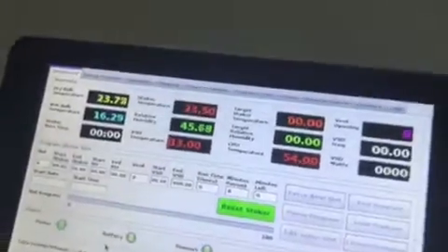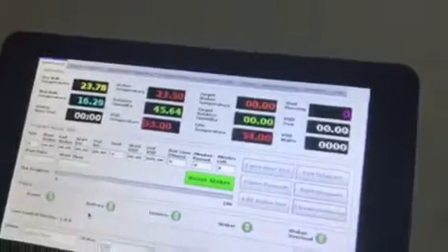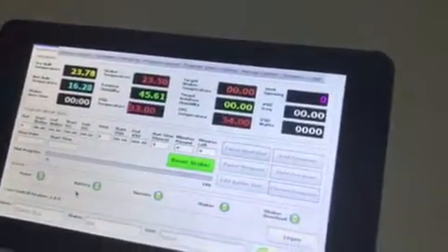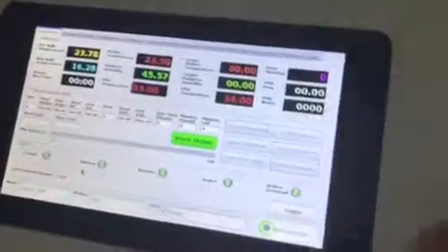So there we can see wet bulb, dry bulb, the stoker temperatures, how big the vent opening is, and there's a whole control cycle that I can set here. If I go to a drying program, I can load a whole program and all the steps that it can follow, the cool down and dampening phases. The history, and then the chart of the actual drying cycle that it will follow.